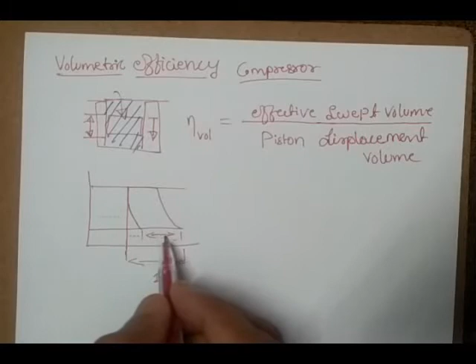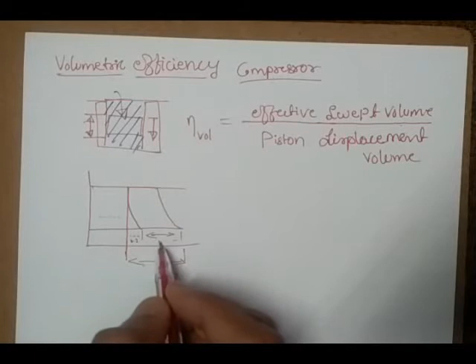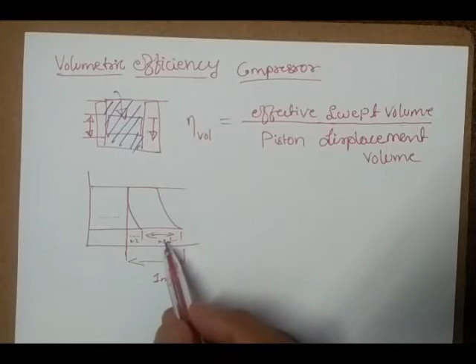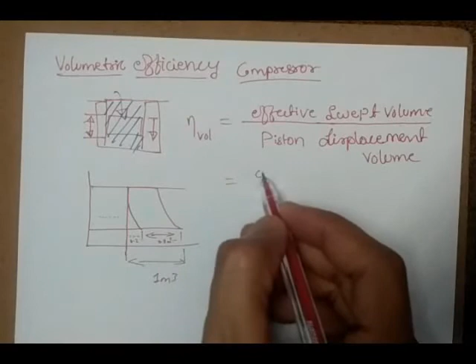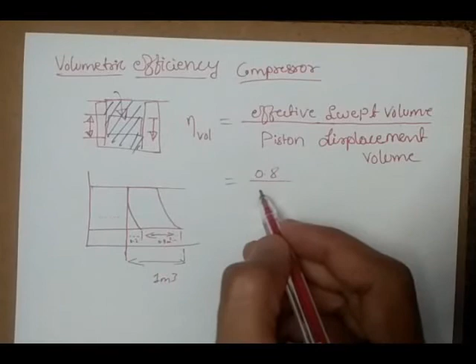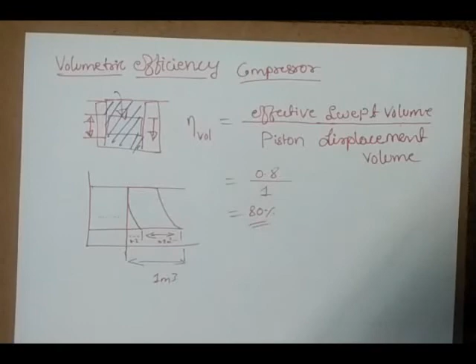So only this much volume is what the compressor takes. Out of 1 meter cube, if this is, say, 0.2 meter cube, then roughly 0.8 meter cube is the effective swept volume. It's just a rough value. So 0.8 by 1, volumetric efficiency is 80%. So as a rough calculation, if only 0.8 meter cube of air is sucked in with a total capacity of 1 meter cube, we will get 80% volumetric efficiency.